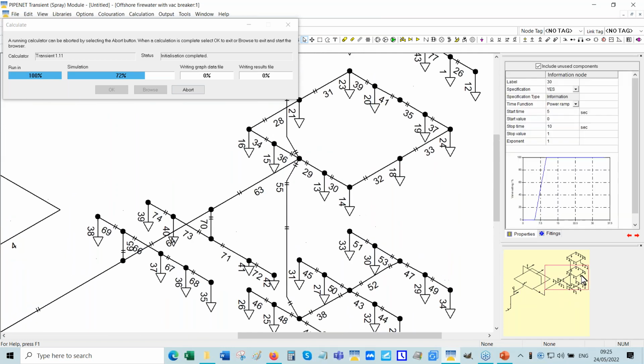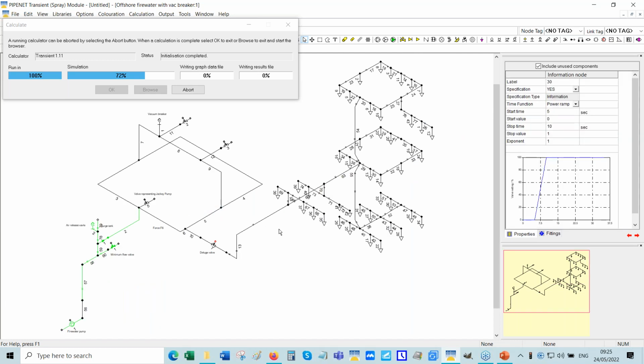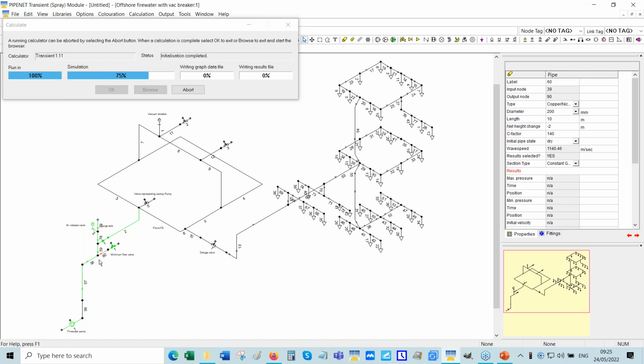This is a more complex deluge system than the one we looked at earlier. So that's why it's taking slightly longer, because there are a lot of things going on. There could be oscillations in the pressure here. And of course, as I said, that pipe here, much to my surprise, I discovered that that's a source of a problem. Okay.